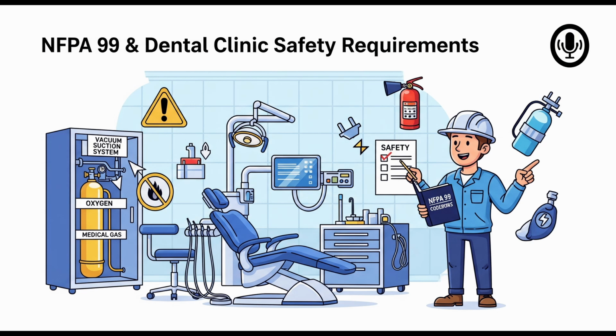Okay, let's use that to recap and answer some of the listeners' initial questions directly. First off, did we find any minimum area or space requirements defined for dental clinics or treatment rooms in this NFPA 99 source? No, not in terms of setting minimum square footage for rooms. The source material doesn't say a dental operatory must be X square feet or a clinic needs Y total area. The space requirements mentioned are functional, tied to the systems. Like what? Like needing adequate clearance around equipment for maintenance access, needing enough room in storage areas to maneuver cylinder hand trucks safely, and those mandatory safety separation distances like the 20-foot clear zone around outdoor gas storage from ignition sources or the 10-foot distance for outdoor enclosures from building doors and windows.